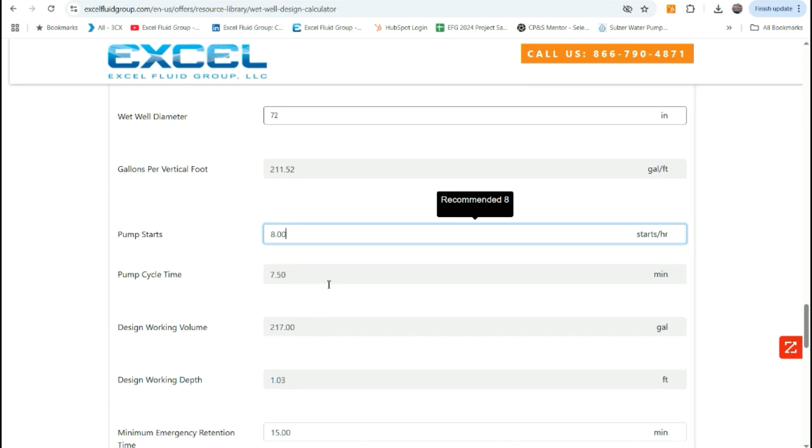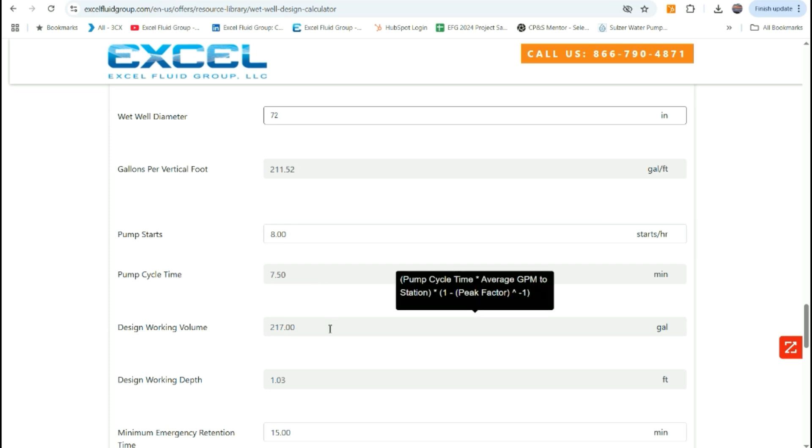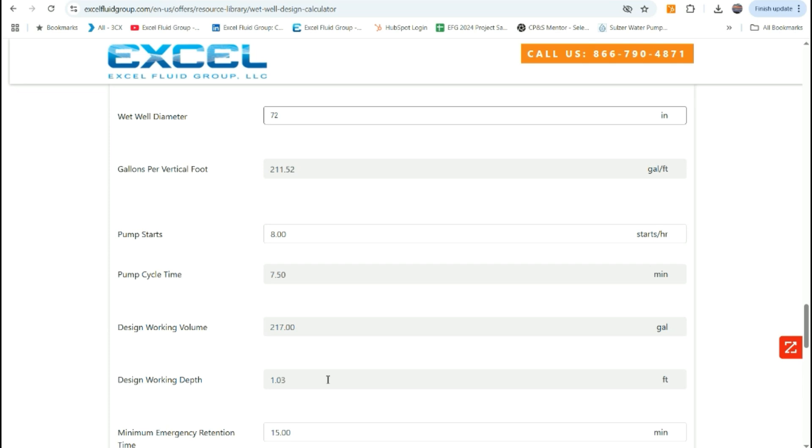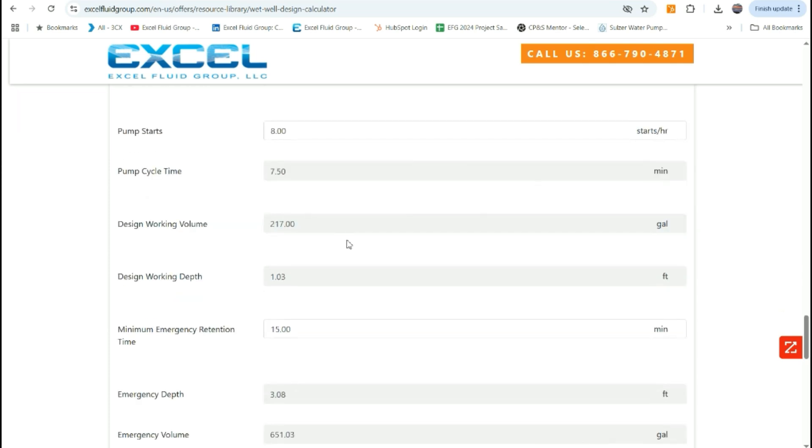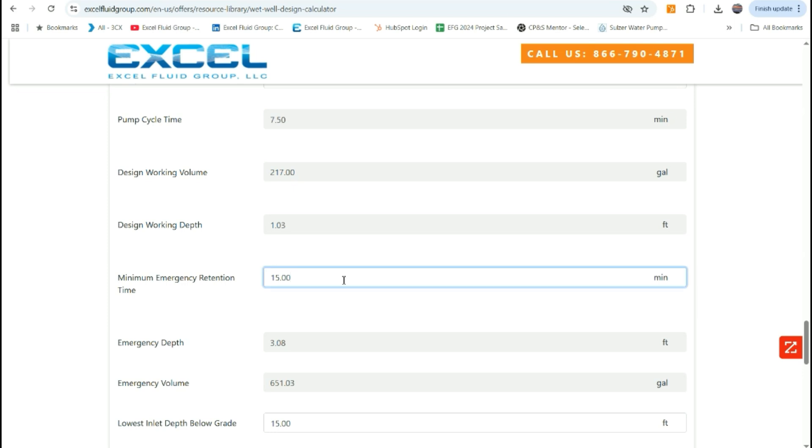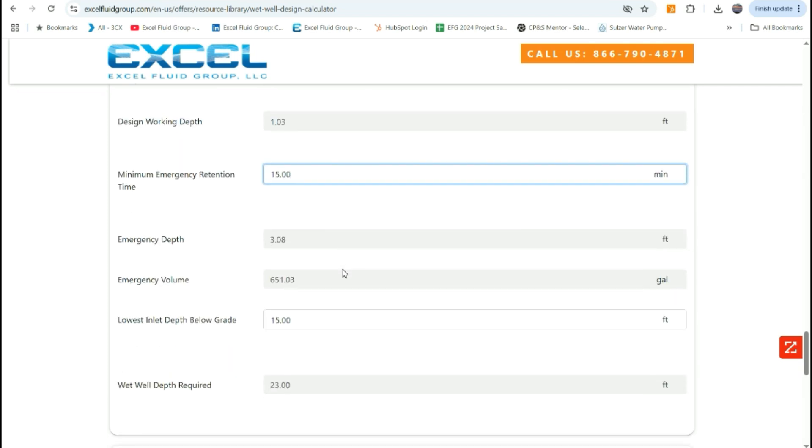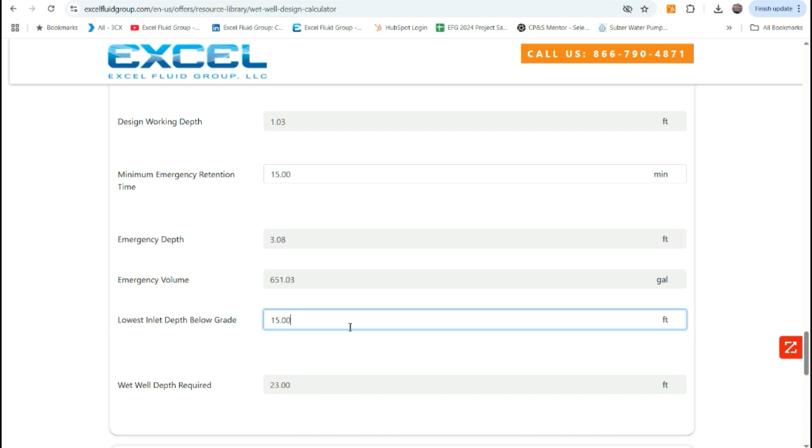Once the starts per hour has been inputted, that calculates your pump cycle time and then the design working volume in your wet well and the design working depth. The next field is your minimum emergency retention time. This can either be as low as zero if you have additional emergency backup equipment like standby pump or generator. However, if we put in 15 minutes in this example, then that shows an emergency depth of three feet above your high water float elevation and then shows your emergency volume in the wet well. Further to that, you would input your invert depth into the wet well, which typically you would find again on the force main profile drawings. Once you've inputted that, that will calculate your wet well depth for this application.